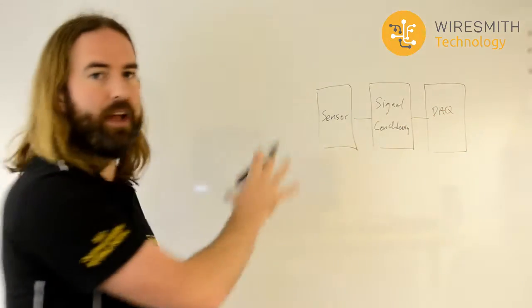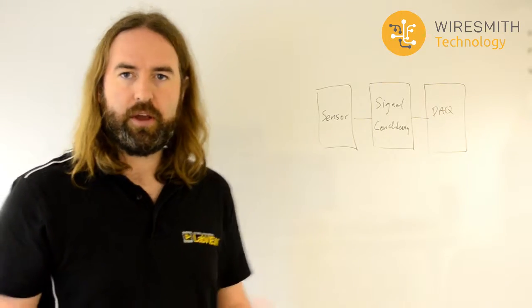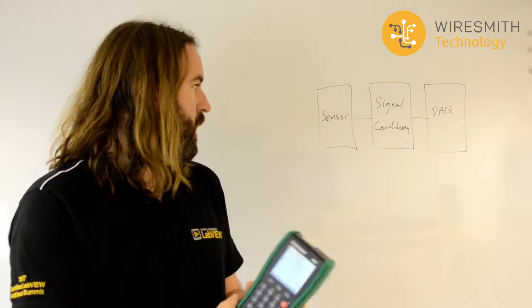And so what system calibration does is it says, rather than depending on the individual calibrations of these components, which may be defined by the manufacturer and might be on different calibration schedules, what we're going to do is take a calibrator, so this is an example of a handheld calibrator, and we're going to either excite the sensor to the right physical phenomenon, maybe using a temperature chamber or a pressure pump, or we're going to inject electrical signals and simulate the sensors with the calibrator, and then we're going to measure what the system does, and produce some calibration curves for the system as a whole. That way we can see whether these individual components' errors might add up and become worse, or they might cancel each other out to some extent. We get a real calibration for the entire system rather than the individual components.